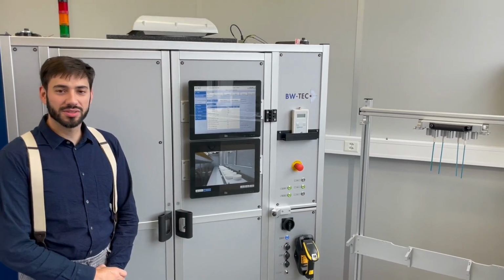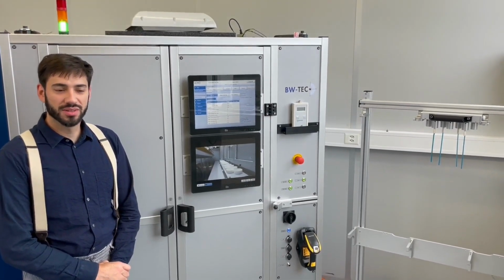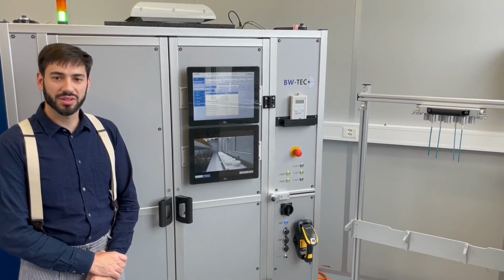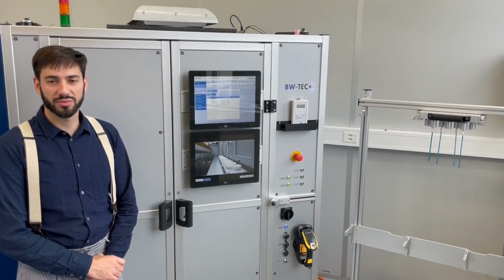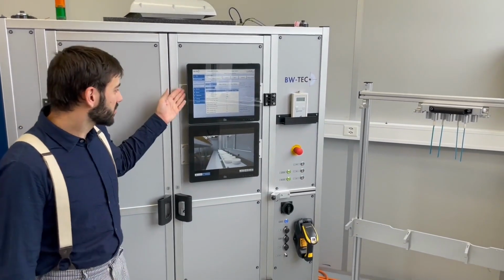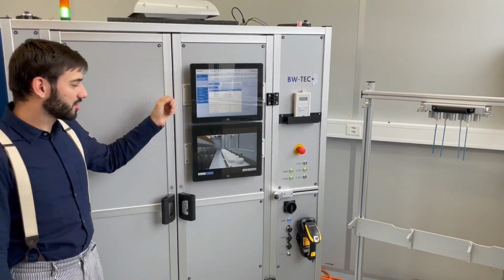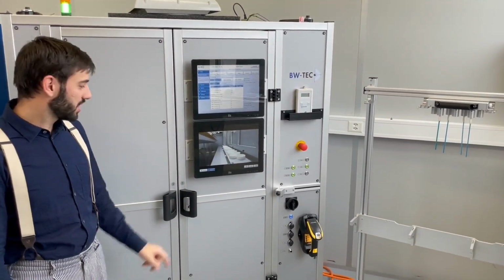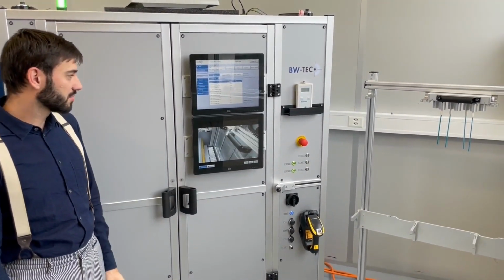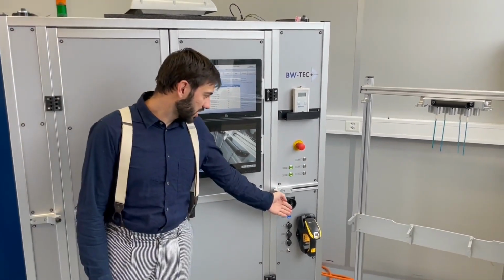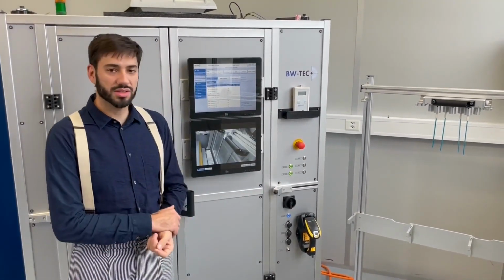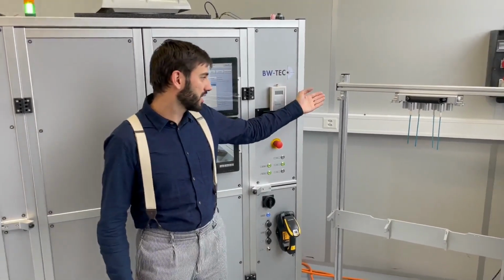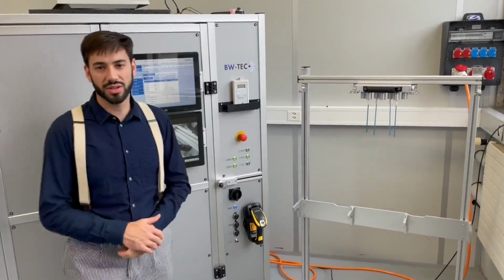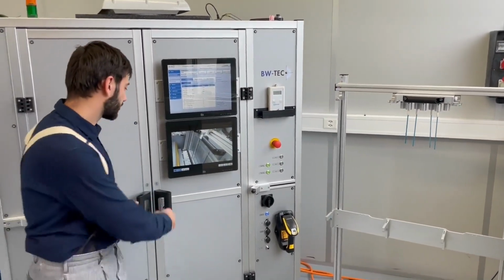This is the 2269 Hydrophilic coating machine. It is made for up to 21 products with a coating length of 400 millimeters. It comes with a standard BW TEC HMI and includes two cameras on the inside for a view of the process. It is equipped with a barcode scanner and a UV measuring device. It also comes with a stand for the extra product trays for switchover.